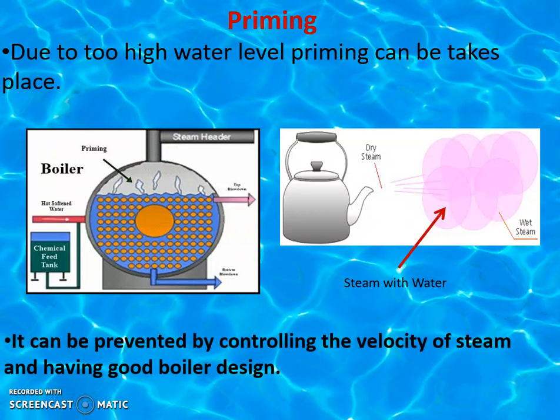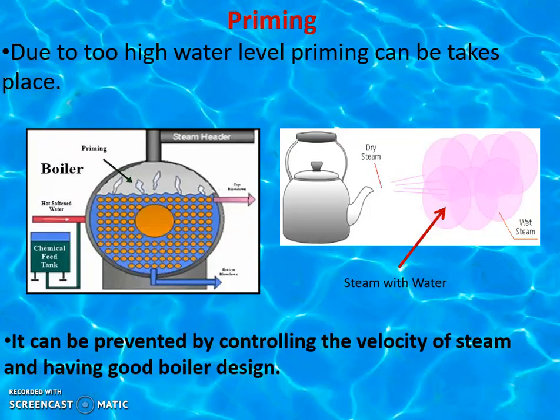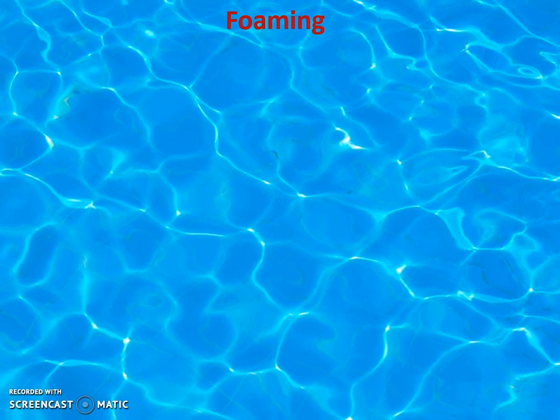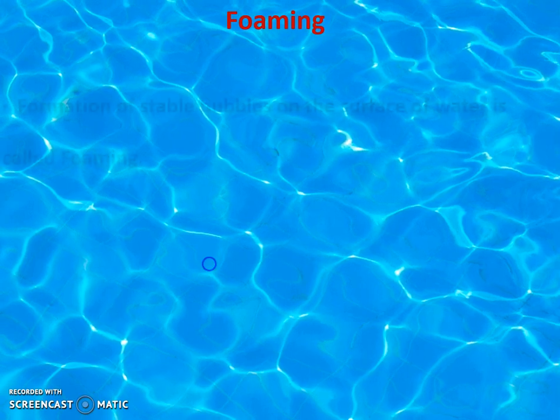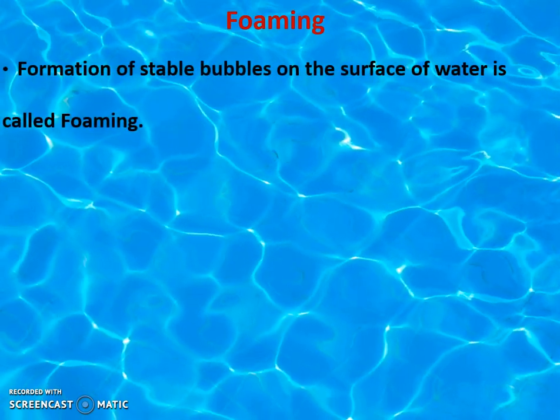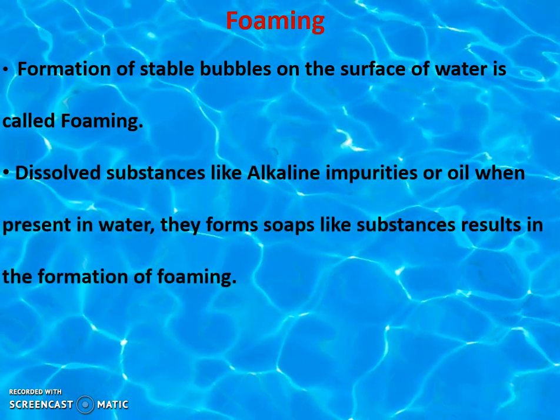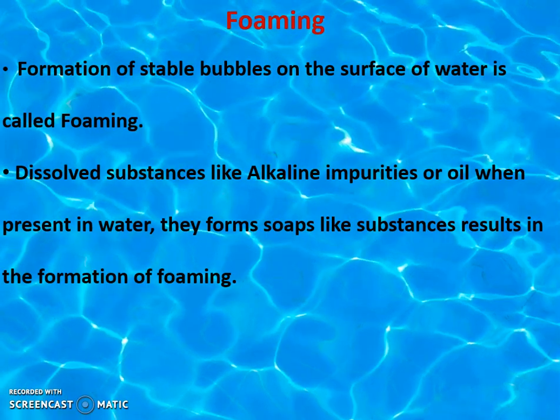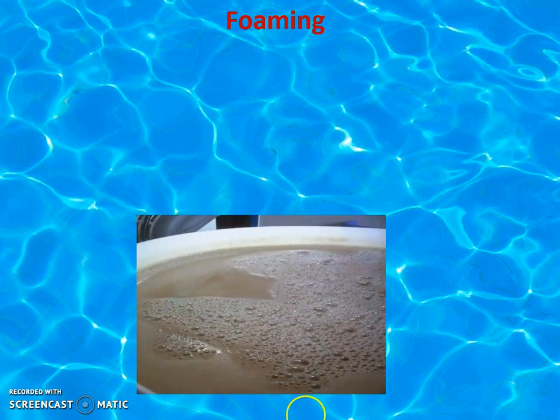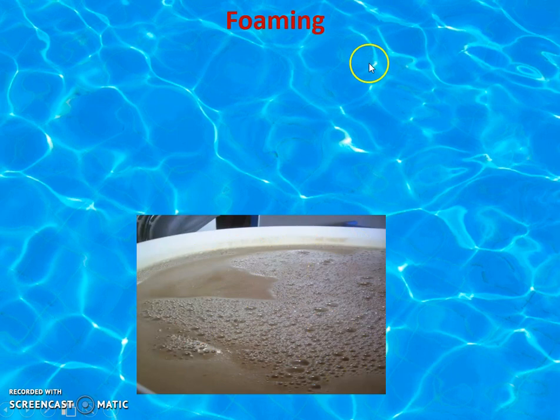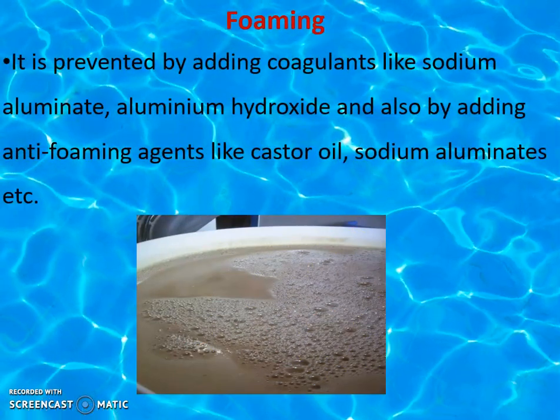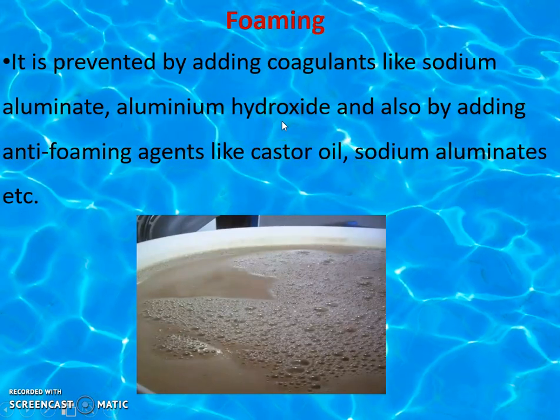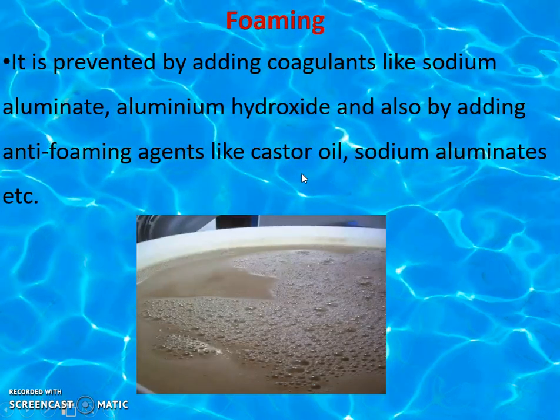Priming can be prevented by controlling the velocity of steam and having a good boiler design. Next is foaming — the name itself indicates foam or lather formation on the surface of water. If water contains dissolved substances like alkaline impurities or oil, they form soap-like substances, resulting in foaming. Foaming is prevented by adding anti-foaming agents or coagulants such as sodium aluminate, aluminium hydroxide, or castor oil.